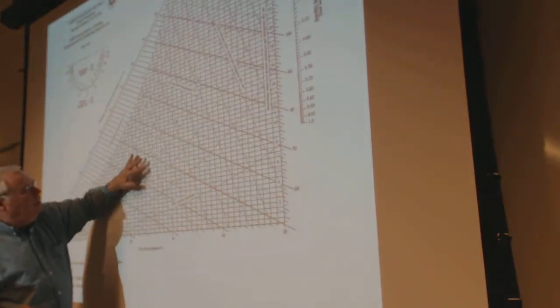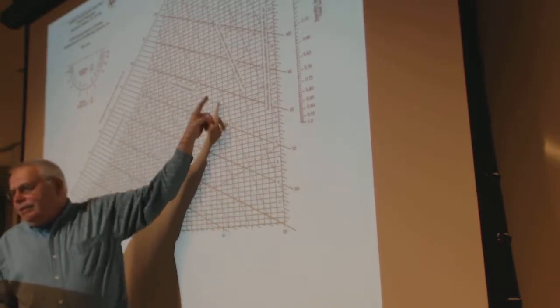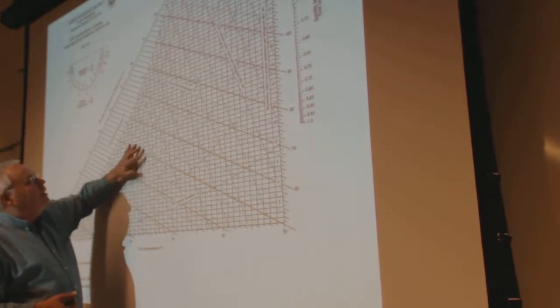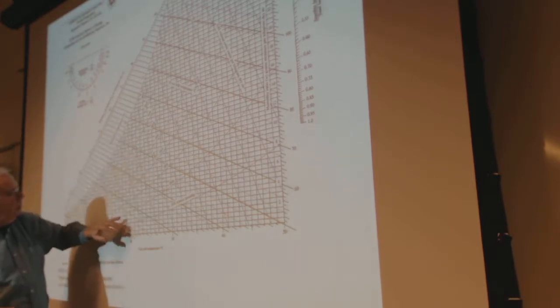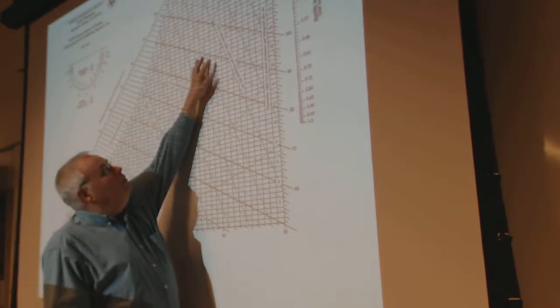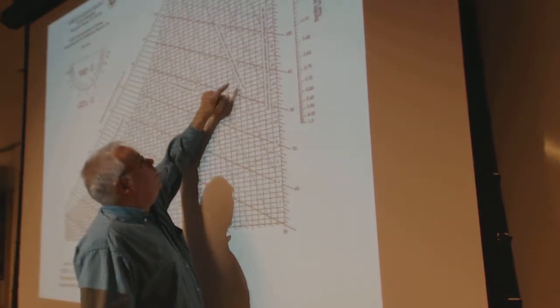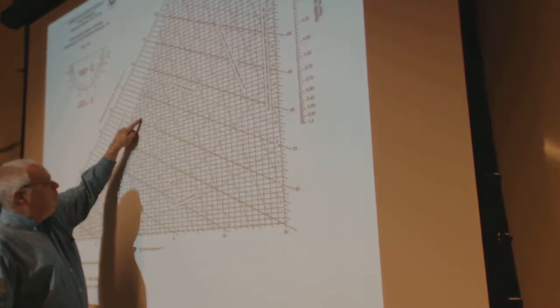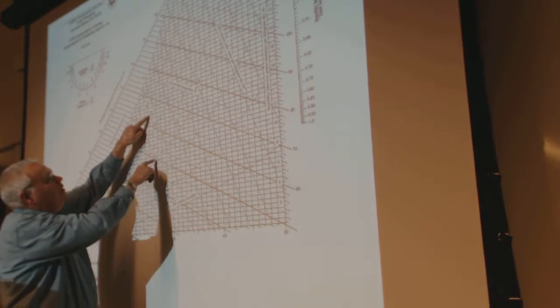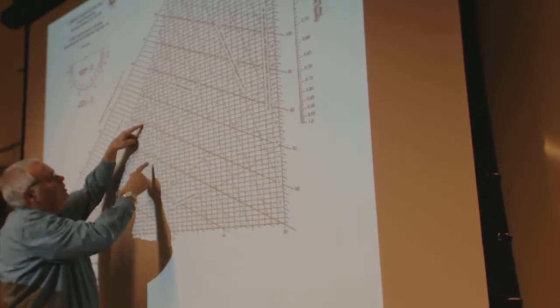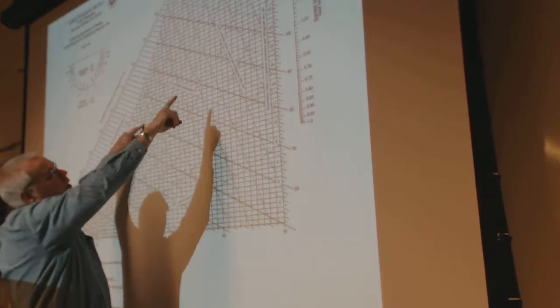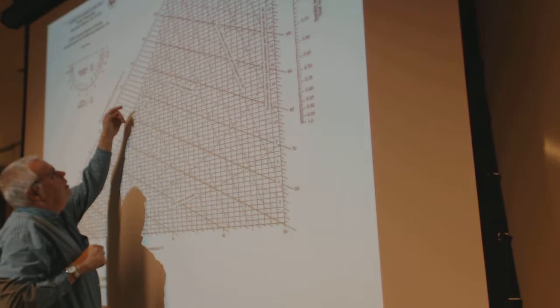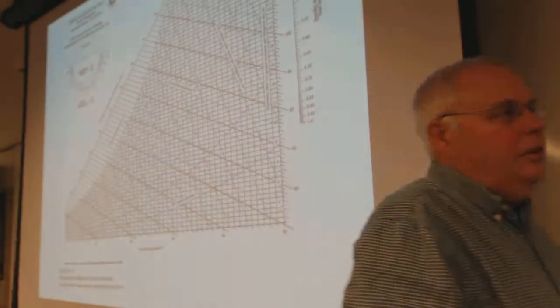Well, how many kilograms of air are in the room? These really steep lines are density of the dry air, without moisture in it, based on ideal gas law. And so, volume, cubic meter per kilogram of air, so it's actually specific volume, so that's 92, 91, 90, 89, 88, 87, 86, and we are at this point, so we're kind of, between 0.86 and 0.87, cubic meters for every kilogram of dry air, and I'm going to say it's a little bit over halfway, so I'm going to call it 0.866.